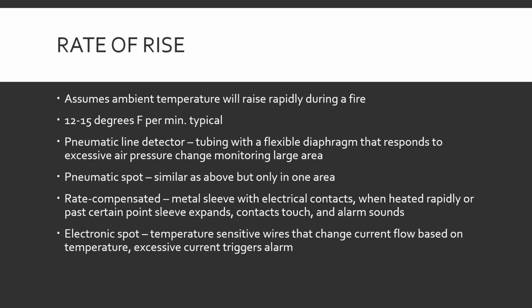Rate compensated. Metal sleeve with electrical contacts. When heated rapidly or past a certain point, the sleeve expands, contacts touch, and the alarm sounds. That's kind of like that bimetallic we talked about, where it heats really quick, it expands, or if the temperature gets up to our 180 that we've been using so far, it'll then expand, it'll close the circuit, and the alarm goes off.